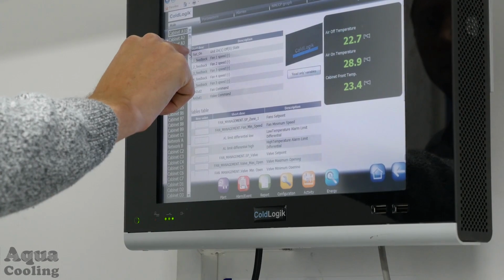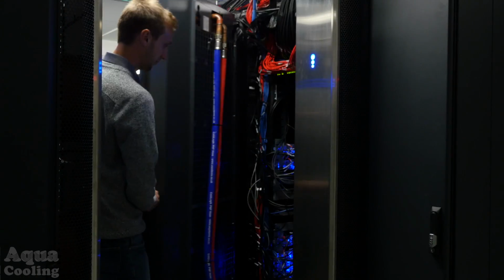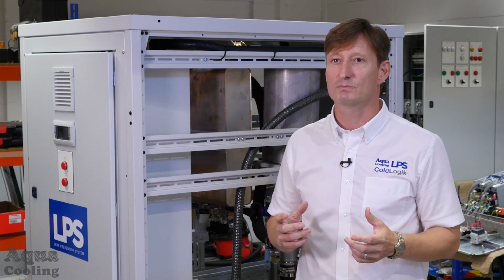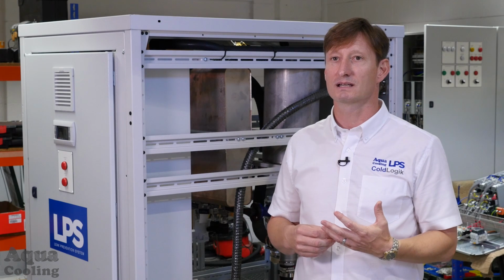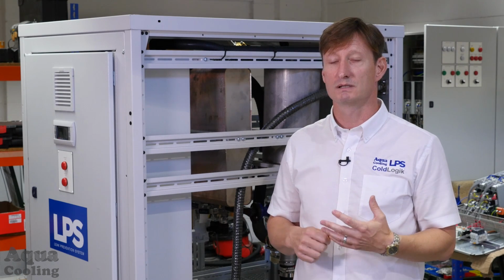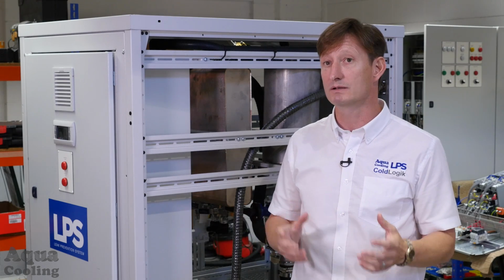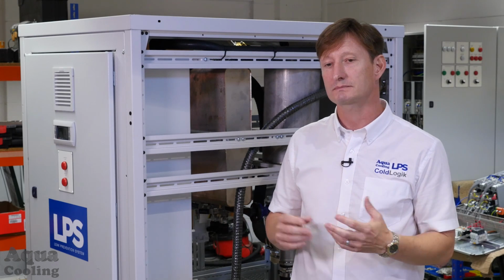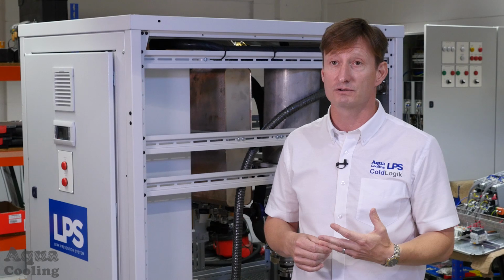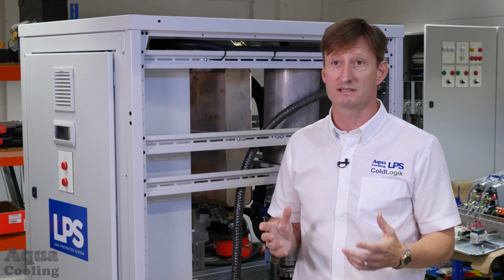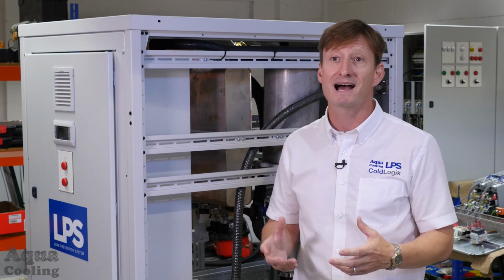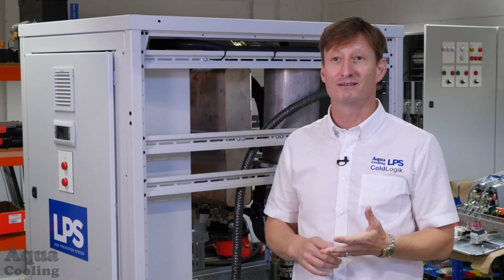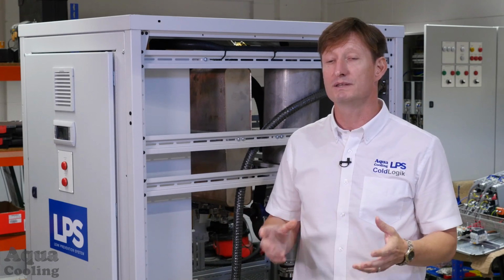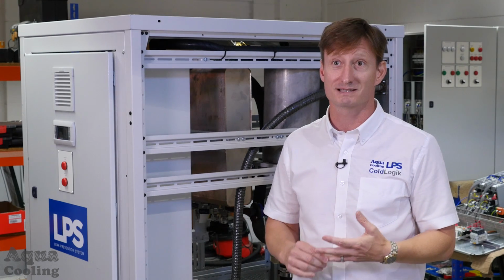One of the major benefits we have for the LPS system is that it's very efficient, having the cooling medium very close to the IT load, and it reduces our electrical costs for running the data centre. Data centre managers should really invest in the LPS system because it can, in most cases, reduce their insurance premiums, because most insurance premiums don't actually cover water damage, whereas with the LPS that is also incorporated. Energy efficiency against normal refrigeration cooling, and also the amount of uptime that is available, because with the LPS you can actually add to your normal resilience. So in our speak, rather than having n+1 or n+n, with the LPS you have n+1+1 or n+n+1.